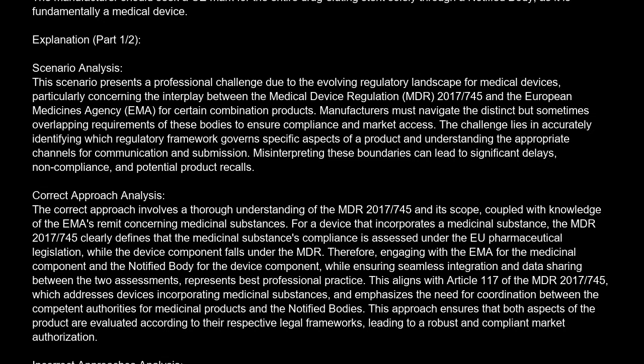The correct answer is B. The manufacturer should seek a CE mark for the entire drug-eluting stent solely through a notified body, as it is fundamentally a medical device. Explanation. Scenario analysis. This scenario presents a professional challenge due to the evolving regulatory landscape for medical devices, particularly concerning the interplay between the Medical Device Regulation, MDR 2017/745, and the European Medicines Agency, EMA, for certain combination products. Manufacturers must navigate the distinct but sometimes overlapping requirements of these bodies to ensure compliance and market access.